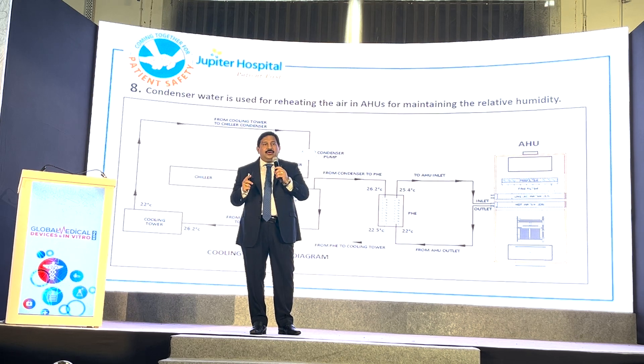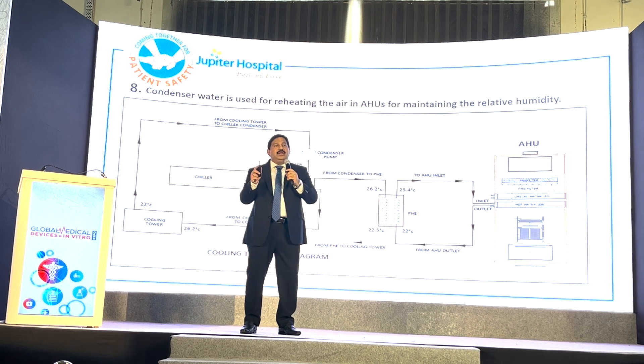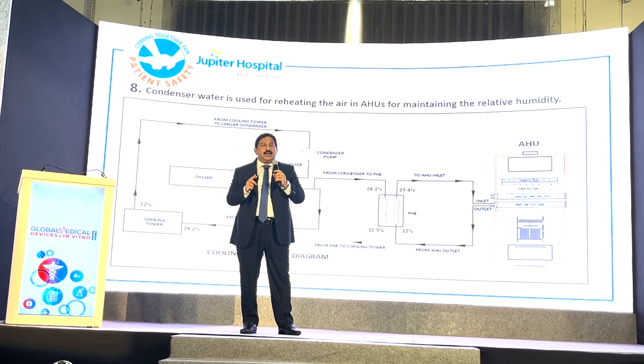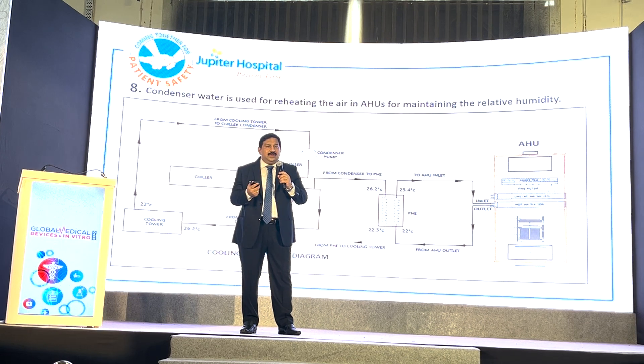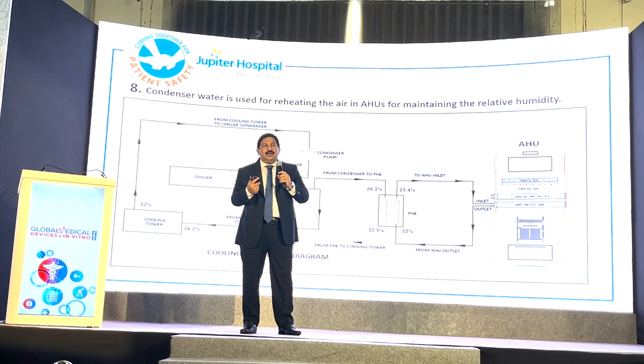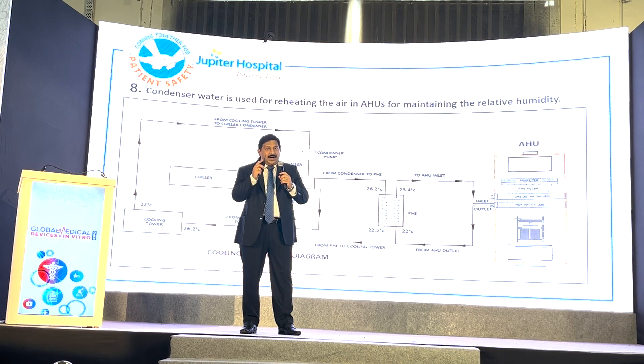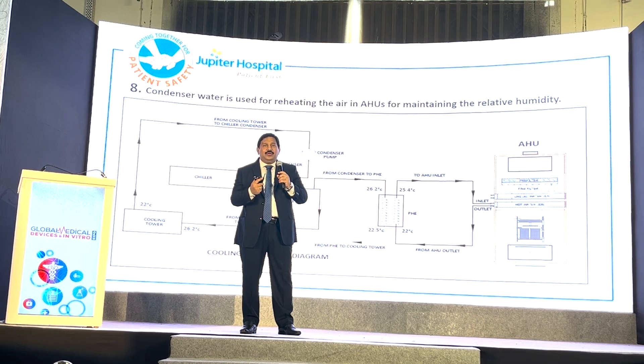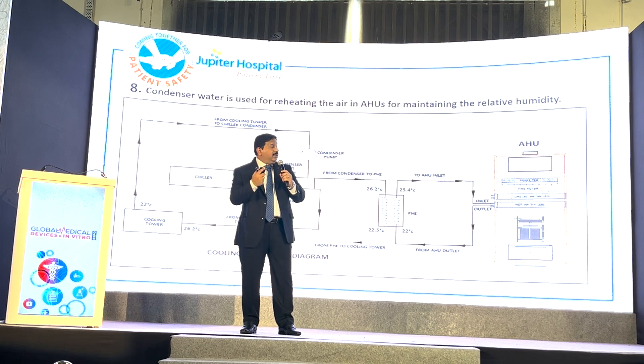We can do one thing. When I am saying 22 degrees — how many times in an entire day are we using CT scan, MRI, cath lab? Maybe 14 to 15 hours maximum. But 9 hours are such that the machine is idle, no one is there inside. And the machine requirement? 26 degrees is also okay. So for at least those 9 hours, can I do something? Even manually, without a BAS — instead of 22 degrees, can you do 24 or 25 degrees? Yes, it is possible. Even if you do 24 degrees, per day on medical equipment alone we can save minimum 200 units. These small savings are going to make a net zero impact and CO2 reduction.